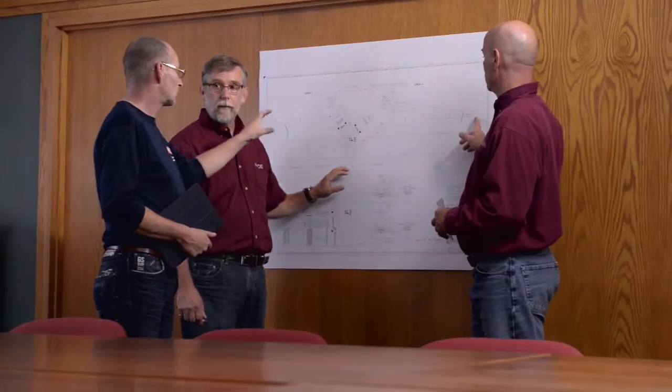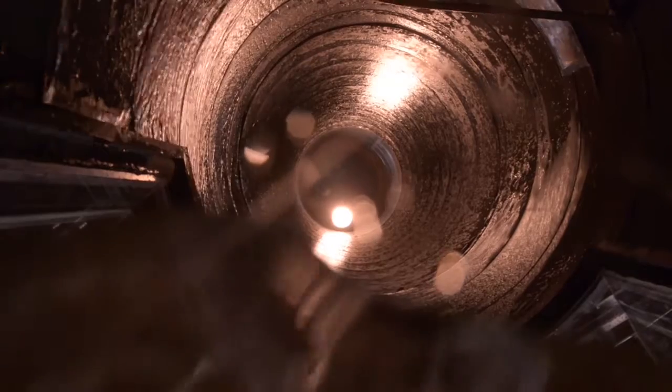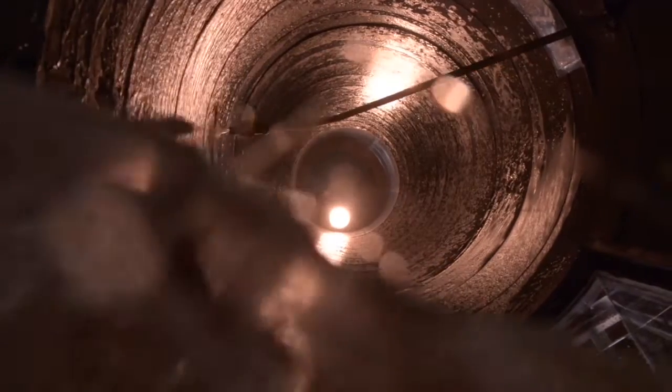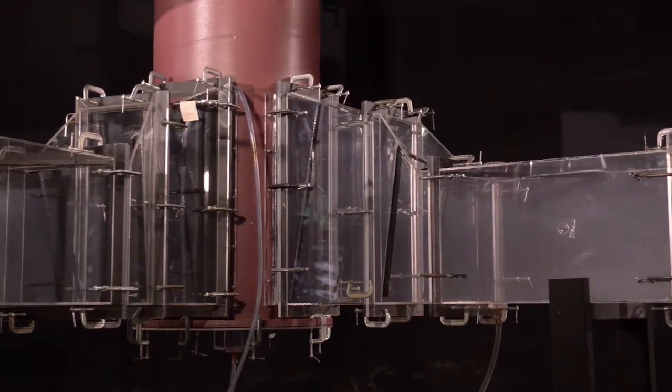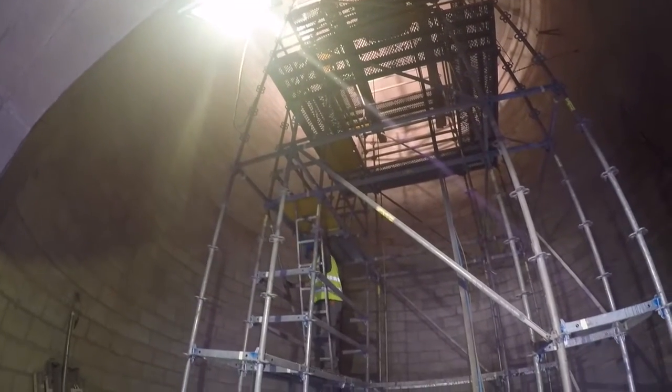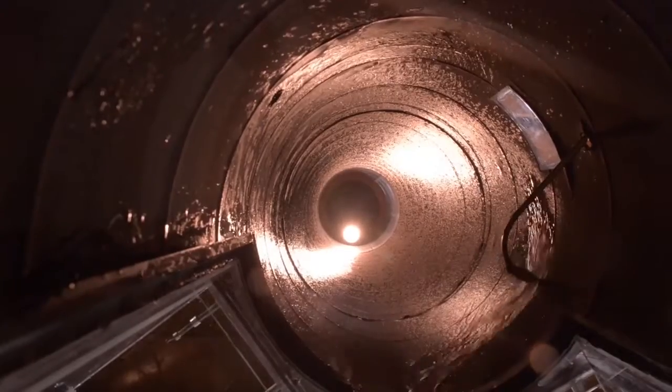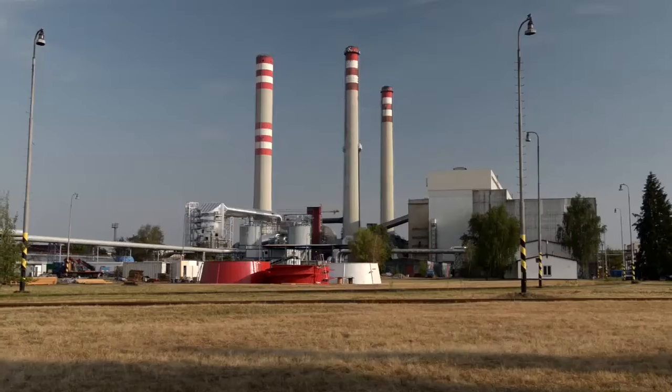Liquid reentrainment from a wet stack is caused by high condensation rate within the liner, excessive gas velocities reentraining collected liquid back into the gas flow, and liner surface discontinuities that can enable reentrainment.